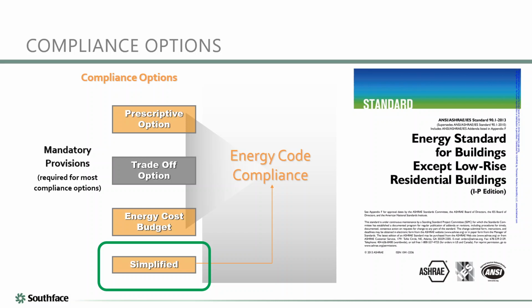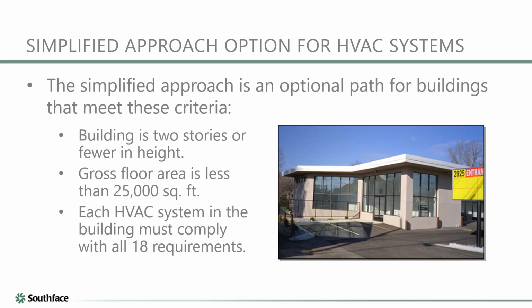This is valuable because the majority of new commercial buildings permitted in this country actually meet the simplified building profile. The statistics that I've seen tend to say somewhere between 80 and 85% of all of the commercial building permits pulled are pulled on buildings that would meet the simple building profile. And here is that simple building profile, which essentially says if you have a building that is 2 stories or less, and 25,000 square feet or less, then your HVAC systems can be deemed to comply with the requirements of the Energy Code if they can check off 18 items from a list. And those items are essentially things like equipment functionality, zone controls, thermostat controls, and basic levels of efficiency.